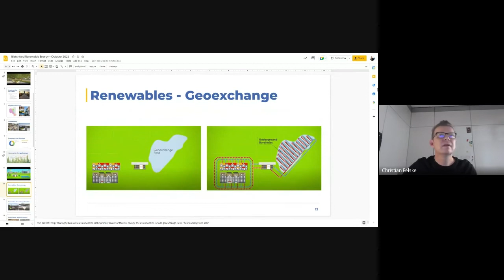The first phase is based on geo-exchange under a stormwater pond in the community, which is part of the Central Park. There are two loops, the ground loop as we call it. There are about 570 wells drilled about 150 meters deep, 6 meters apart, carrying a fluid to Energy Center 1, where we have a very efficient heat pump located, which transfers that energy.